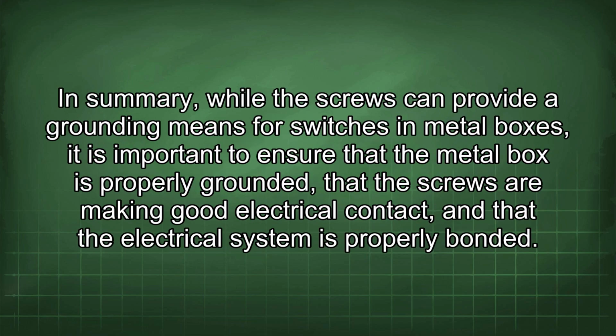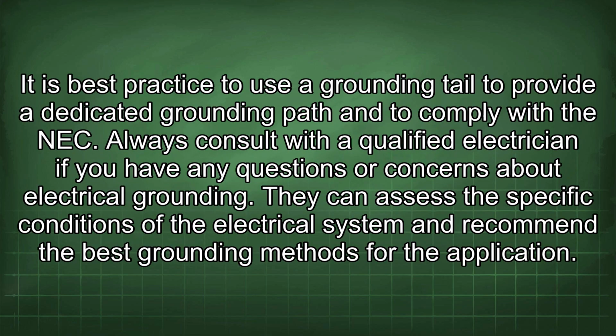In summary, while the screws can provide a grounding means for switches in metal boxes, it is important to ensure that the metal box is properly grounded, that the screws are making good electrical contact, and that the electrical system is properly bonded. It is best practice to use a grounding tail to provide a dedicated grounding path and to comply with the NEC.